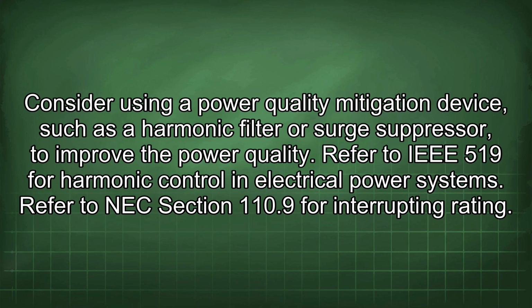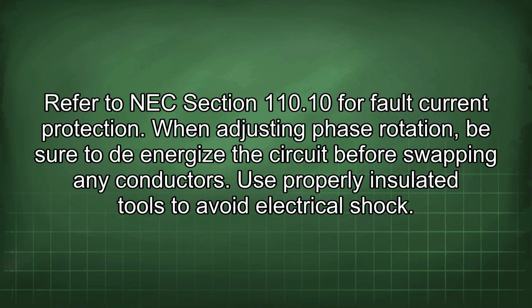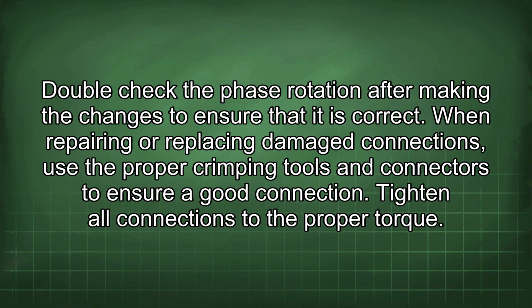Refer to NEC section 110.9 for interrupting rating. Refer to NEC section 110.10 for fault current protection. When adjusting phase rotation, be sure to de-energize the circuit before swapping any conductors. Use properly insulated tools to avoid electrical shock. Double-check the phase rotation after making the changes to ensure that it is correct.